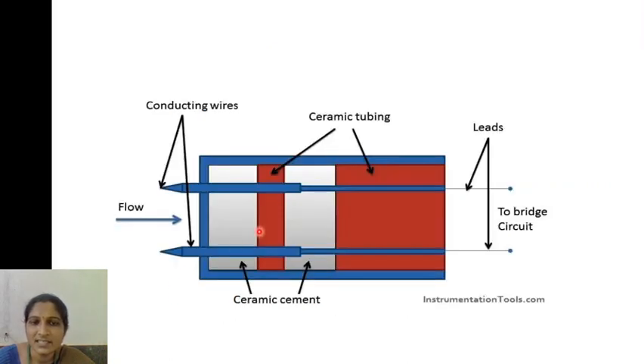Coming to the construction diagram of the hot wire anemometer, you will have the ceramic tubing. In between the ceramic tubing, you will place ceramic cement. Under this ceramic tubing, you will place the conducting wires. These two are the conducting wires, and at the end of the conducting wires you will place the leads. You will connect wires so that they can be connected to the Wheatstone bridge. So this is the construction diagram of the hot wire anemometer.